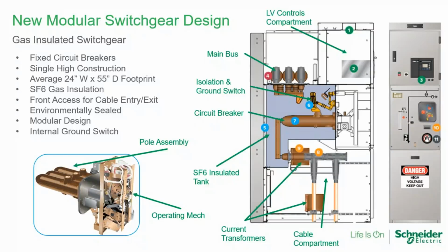If you look at the breaker on the bottom left, it looks fairly different, but the main components are the same. So you'll have the pole assemblies in the rear, the operating mechanism in the front, and since it's a fixed mounted circuit breaker, it's not going to be withdrawn, so you don't have to have a truck underneath it. So I see we got a question here.